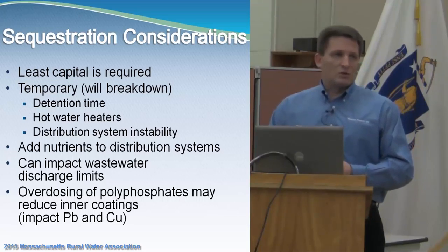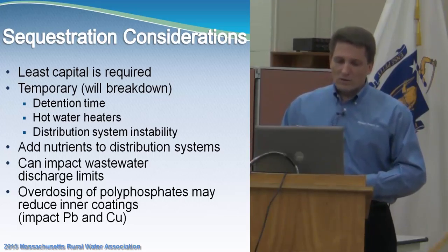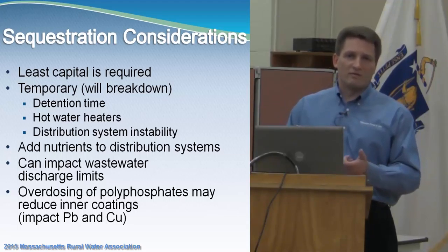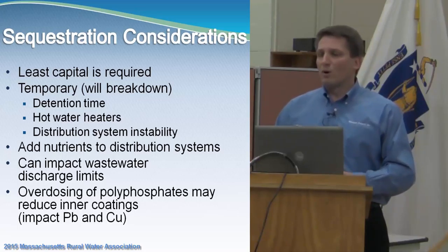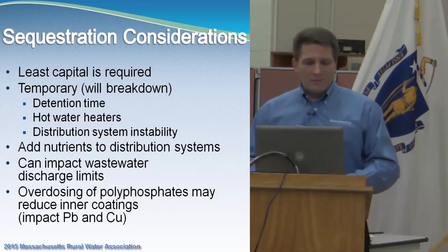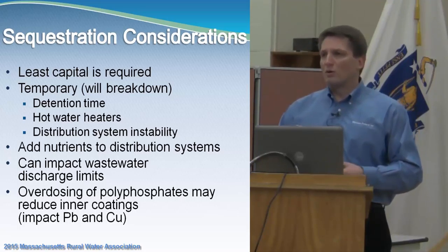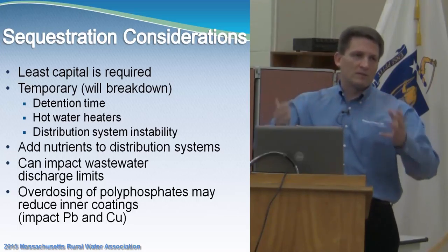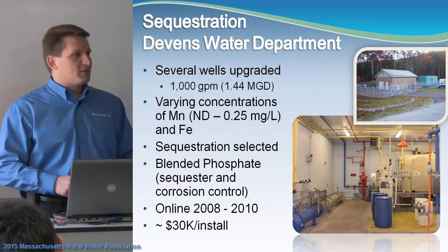Sequestration adds nutrients to the distribution system, specifically phosphates. Organisms want to grow on phosphate, and that will impact anyone with a wastewater treatment plant discharging to a river, where phosphate limits are getting tighter and tighter. If you think about using a sequestrant, talk to your wastewater department about those secondary impacts. Another caution with polyphosphates: if you're doing corrosion control, an overdose can be problematic for the coatings that have formed to allow you to pass your lead and copper rule samples.